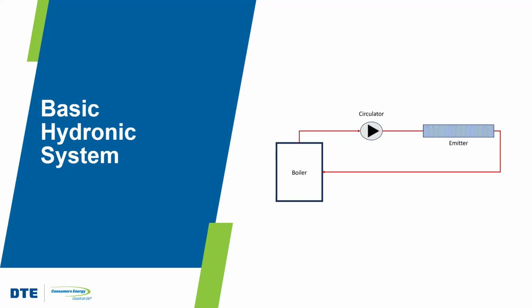And instead of imparting that heat to air, it's imparted to water this time, which is circulated around through a piping system. There's a small pump instead of a fan that you would have with your furnace. And that water then flows, instead of flowing to outlets as you would with a forced air system, to what we call emitters, right? And it enters at one temperature and it leaves at a lower temperature as it gives up heat to the surfaces and to the space, right?